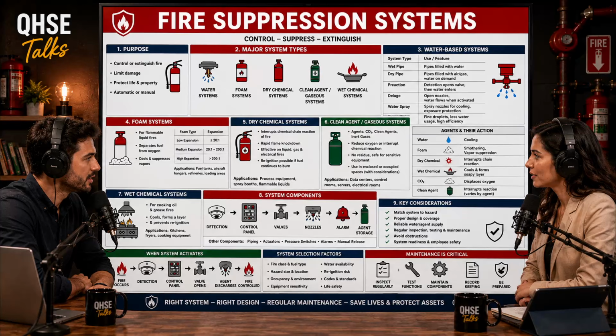Speed is absolutely critical, but safety engineering is an exercise in balancing competing risks. The delay in a dry pipe system is a calculated trade-off. So you're accepting a slower response time to eliminate the risk of a burst pipe. Exactly. Yes, because of that 60-second delay, the fire will likely grow a bit larger. You might have 4 or 5 sprinkler heads pop open instead of just 1 or 2. So you get more fire damage and more water damage. True, but it is vastly superior to having a frozen, ruptured pipe providing absolutely zero fire protection when the building burns to the ground. That's a very fair point.